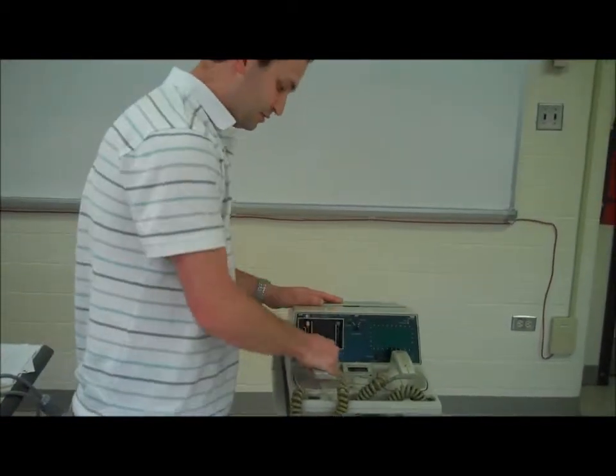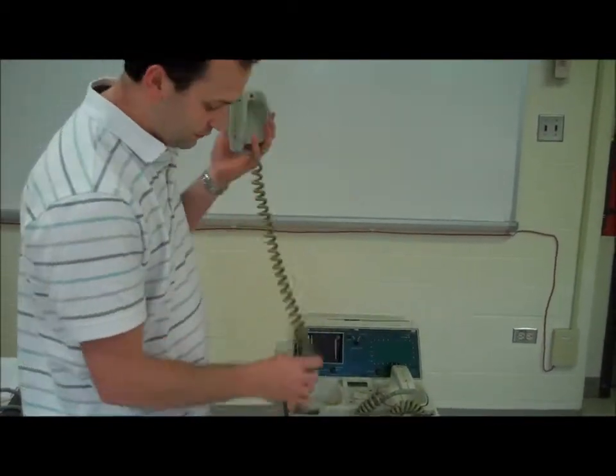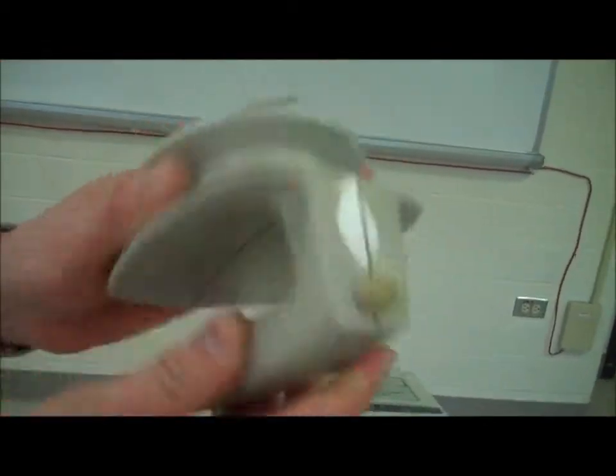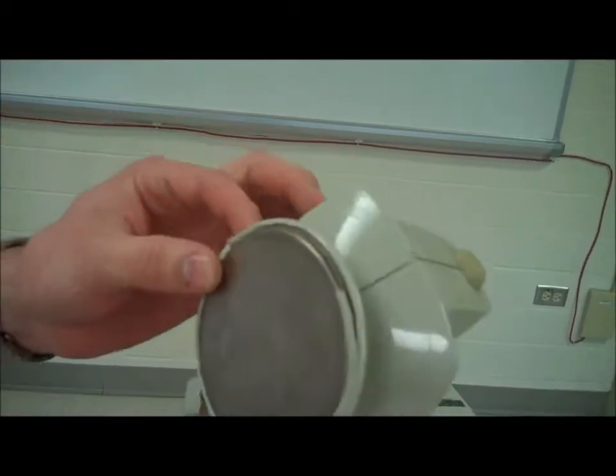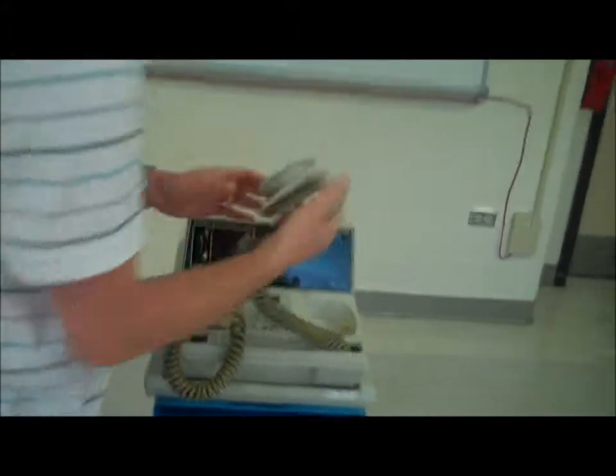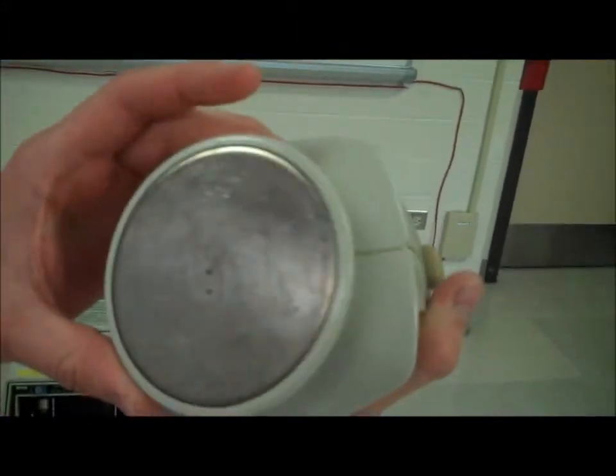And also check these paddles to see if the cords are okay. Make sure there's no breakage here on the corners. Like here's a cracked piece on the paddle, so this paddle part needs to be replaced. And we can check the other one. So this paddle looks okay. I don't see any cracks on that.